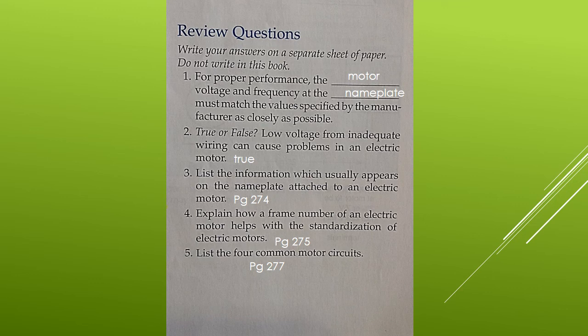Question three, list the information which usually appears on the nameplate attached to an electric motor. And that is frame and type, horsepower, motor code, cycles in hertz, phase, revolutions per minute or RPM, voltage, thermal protection, amps or amperage, time, ambient temperature or temperature rise, service factor, insulation class, and NEMA design.